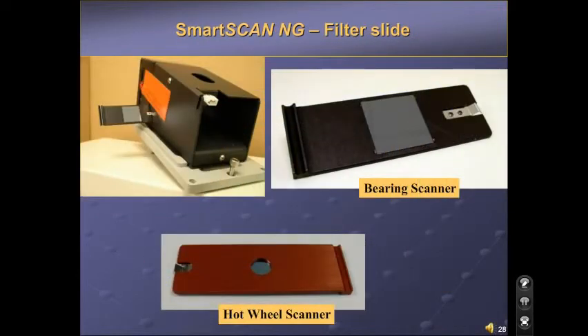Each Type III scanner will be shipped with a black filter frame in place. If the scanner is going to be used as a hot wheel, we will supply a red filter frame in a separate bag. Whether you use the black or red frames, it is important to note that in order to calibrate a scanner, the black frame must be in place.